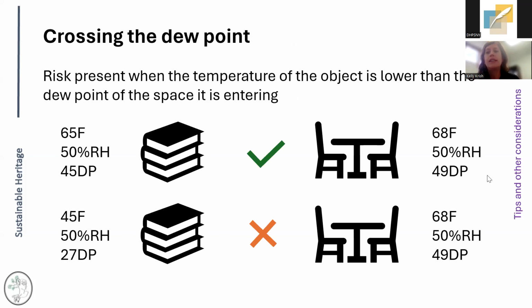As long as the temperature is higher than the dew point of the space it's going into, you're okay. So you just want to compare those two different areas and make sure that if there is a risk of condensation, we would bag the object and let it equilibrate before exposing it to the new conditions. I'll just add too that you can generally assume temperature equilibration is pretty fast, a couple of hours or so. Generally the objects are going to be the same temperature as the space they're in unless you've just brought them in.